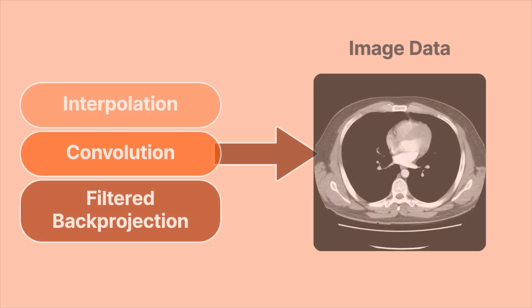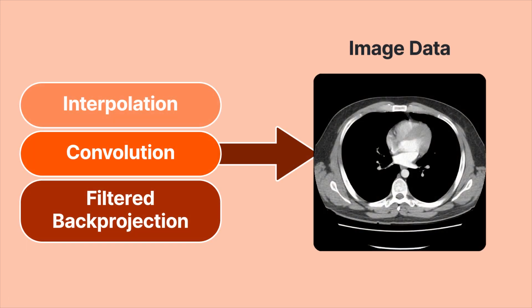So just remember, three steps to the image reconstruction process. First is interpolation, which is unique to helical scanning. Next is convolution, with the application of a reconstruction algorithm. And then finally, filtered back projection.